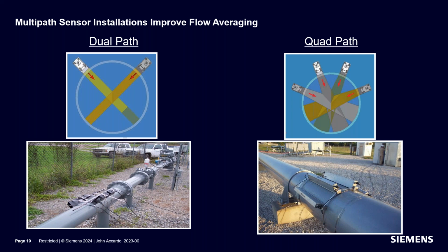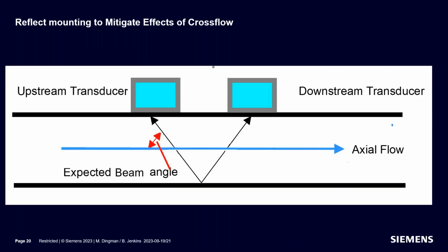Okay. All right, thanks. So anyway, looking at this combined with the next slide, we see transducers mounted in reflect. And you see the sonic beam angle traveling across the pipe and back. And any transit time clamp-on flow meter has to, by nature, assume that the flow is axial, because it has to calculate the refraction angle in order to be accurate. And so when you have an axial flow, if I'm in reflect mount, I know what my refraction angle is because I've measured my speed of sound, and I can compute what the angle of the sonic beam is relative to the flow direction.